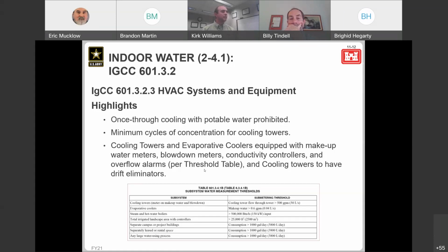And then the last one is cooling towers and evaporative coolers equipped with makeup water meters, blowdown meters, conductivity controllers, overflow alarms, and the cooling towers will have drift eliminators. There are thresholds with all these items. I put the table here with the thresholds for those of y'all that run into that. It's extra items that you need to have, but they're tools to help you know how your system's operating and determine if you have issues later. And the cooling tower drift eliminators are an extra option that you can get from your equipment manufacturer. They're not a rocket science feature. They're just good at keeping the water from leaving the fill and can help keep water in your tower.